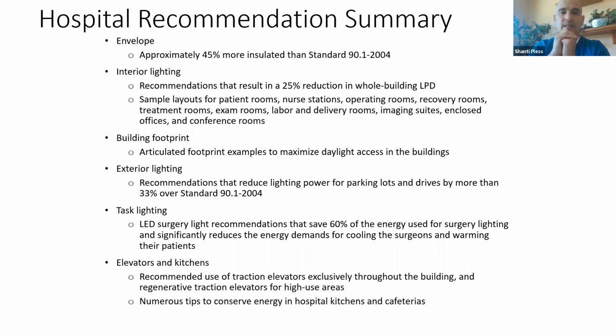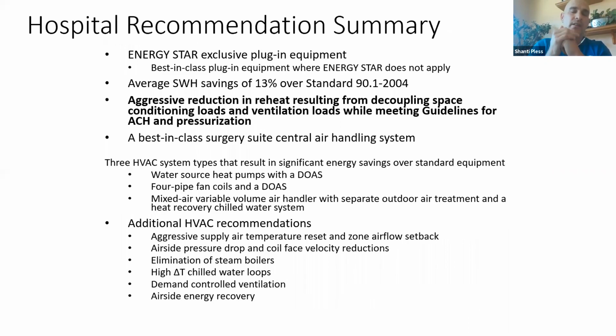On the mechanical system side, reheat is often almost half the load in a large hospital. There's a handful of strategies for aggressive reduction in reheat by decoupling your space conditioning loads from your ventilation air change loads for pressurization requirements. We'll hear from Travis and Kaiser in a minute on how they're implementing strategies like this.